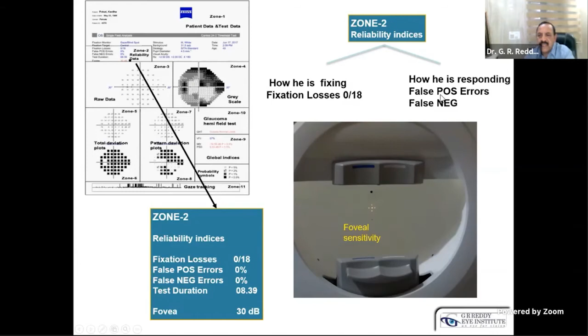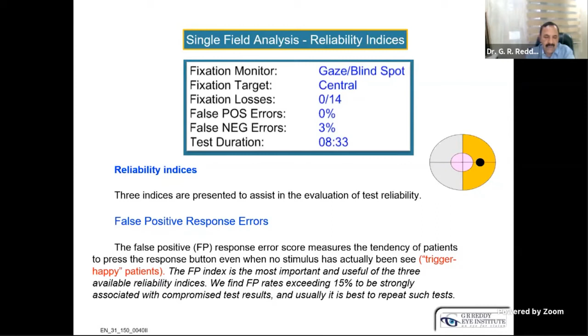The tested area is retested with a dimmer light for which the patient should not respond, but he responds. Or the machine creates an atmosphere as if the stimulus is being projected, when actually there is no projection of any stimulus, and he responds. If the false positives are more than 15%, that is a compromised test, and we have to repeat the test. Coming to the false negatives, that means an inactive patient not responding. The tested area is retested with a brighter stimulus for which the patient should respond, and the patient is not responding. Sometimes even up to 20% can be accepted. Even in advanced glaucomas, we may find a higher rate of false negative errors.